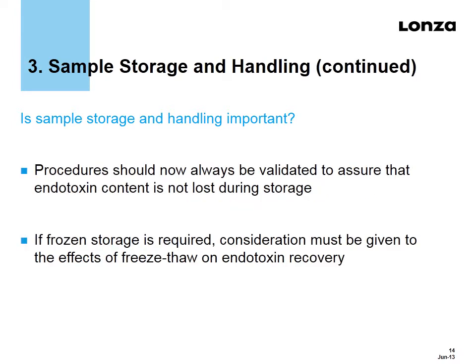The document goes on to state that procedures should now always be validated to assure that endotoxin content is not lost during storage, and that if frozen storage is required, consideration must be given to the effects of freeze-thaw on endotoxin recovery. The previous thought was that samples for endotoxin testing could be stored at 2 to 8 degrees for up to 24 hours before testing, and that the sample should be frozen if the sample could not be tested within 24 hours. The FDA has changed their opinion of that practice since the original document.